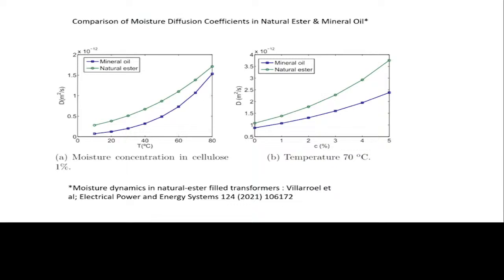So this movement is very important. Unless the moisture gets out of paper in time and into the oil, you are going to see a non-equilibrium condition and its effects on the paper and the oil. So you are going to see PD effects, because the moment moisture comes to the paper, please understand this, it is going to increase the conductivity of the paper. The resistivity is going to go down. So when the resistivity of the paper goes down, you are opening up chances of PD, partial discharge, due to the higher conductivity on paper.